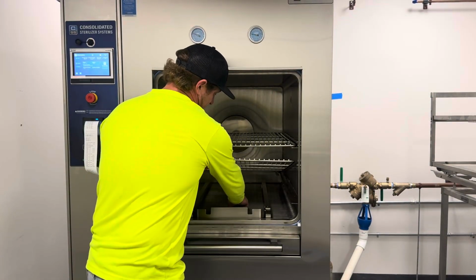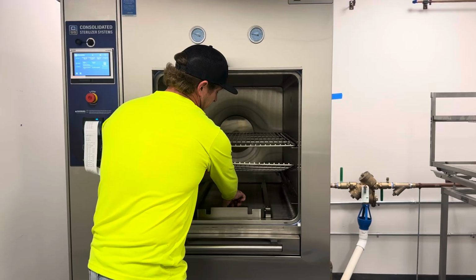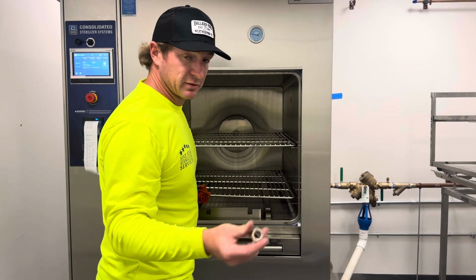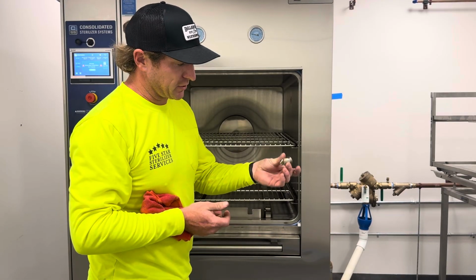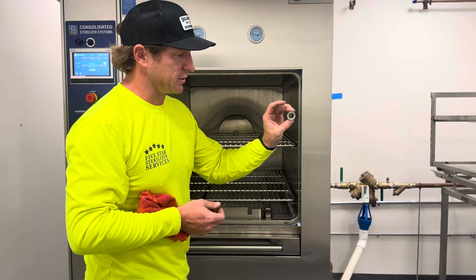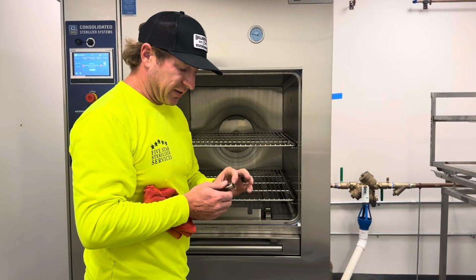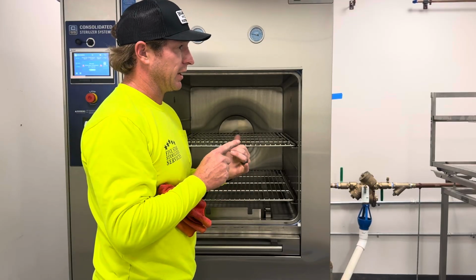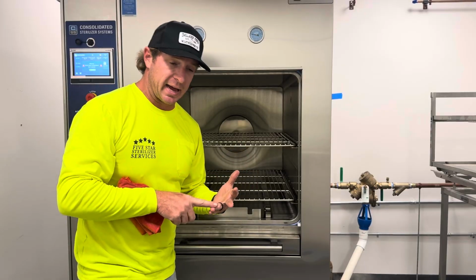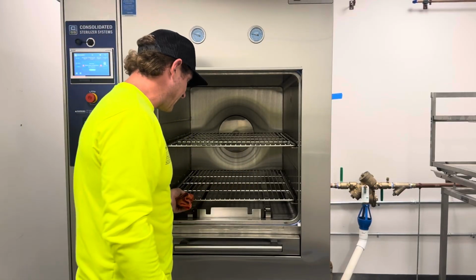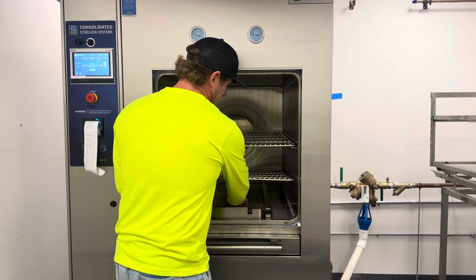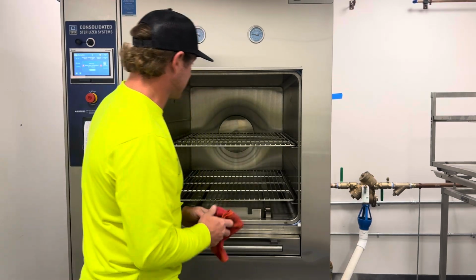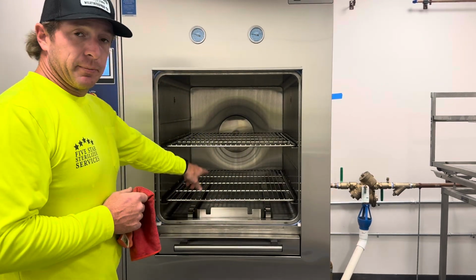To remove this chamber drain strainer, inspect it for foreign material, foreign debris, and make sure this is clean. Take it to a sink, dump it out. Any foreign material, whether it be pine shavings, broken glass, soil, tape, bottle caps, pipette tips, etc. We need to keep that clean.